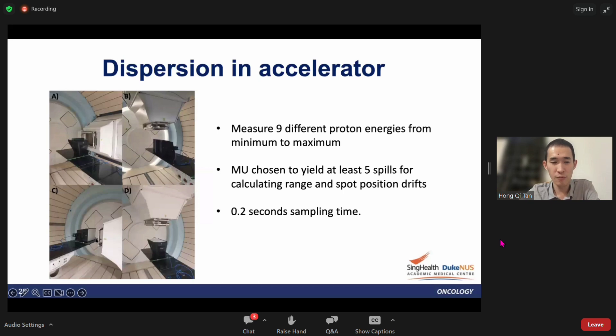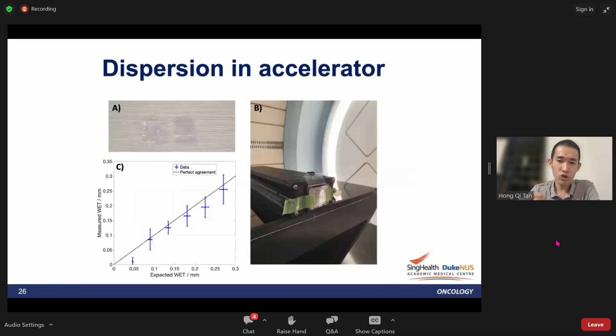To show that the Ranger is suitable for measuring range errors, we did simple measurements using plastic of about 50 microns. We showed that the Ranger is able to detect a range difference down to 0.1 millimeters, so it's certainly sensitive enough to measure the delta R.